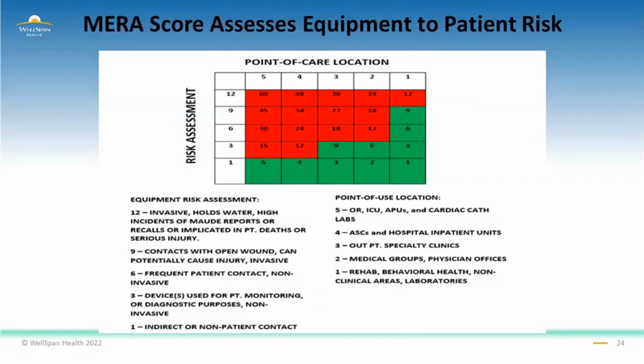The giraffe bed came in as a 60, and it's not invasive, yet the robot, which is used in surgical procedures, comes in as a 5. The difference is the giraffe bed comes into contact with the infant directly. It also has humidified air borne from a reservoir that holds water. The infant breathes that air inside the bed. If that reservoir is not cleaned properly, it can collect mold and bacteria, which can create extraordinary risk to NICU babies. Again, the robot, a mere score of 5 due to its indirect contact with the patient, and the giraffe bed that poses greater risk, and its attachments come into direct contact with the patient.